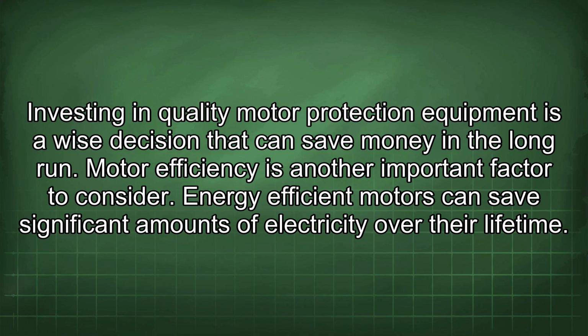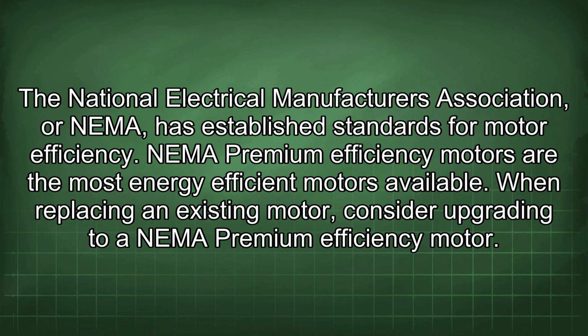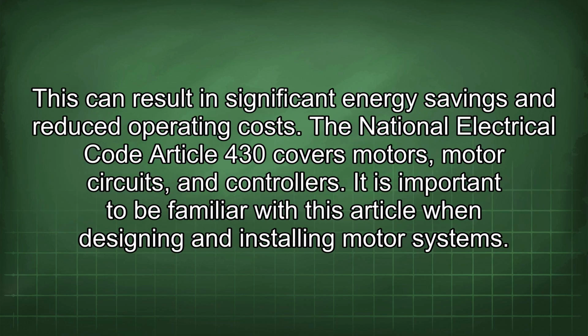Motor efficiency is another important factor to consider. Energy-efficient motors can save significant amounts of electricity over their lifetime. The National Electrical Manufacturers Association, or NEMA, has established standards for motor efficiency. NEMA premium efficiency motors are the most energy-efficient motors available. When replacing an existing motor, consider upgrading to a NEMA premium efficiency motor. This can result in significant energy savings and reduced operating costs.